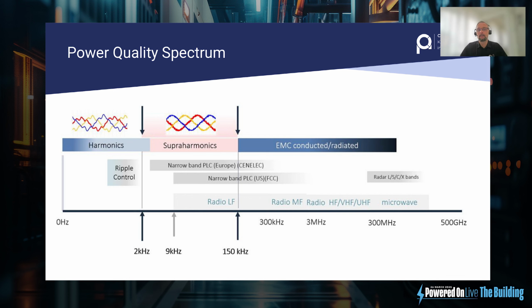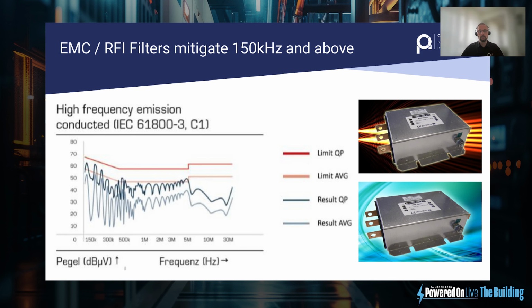Supraharmonics sits in the middle, and until recently, people would probably argue it doesn't exist because there's no standard requiring you to measure it, even though there were devices available to measure it and problems being identified with noise being created here. More today, the standards have caught up and are catching up to mitigate the problems they're seeing here, as the technology has shifted, where the technology is creating the noise in the spectrum from harmonics into supraharmonics. The standards are now realizing, okay, we're going to have to start putting some measures on this now, because we're starting to see issues in production.